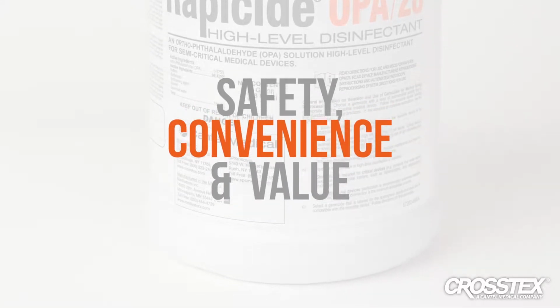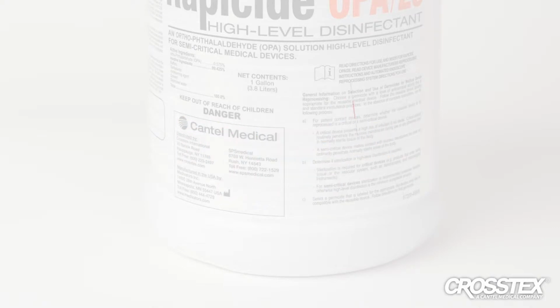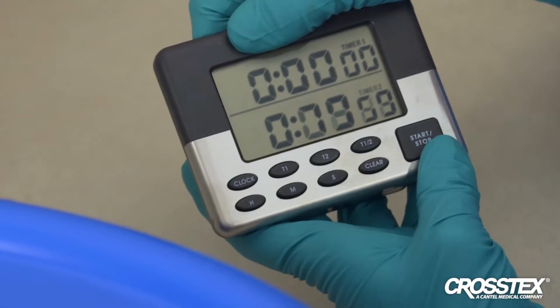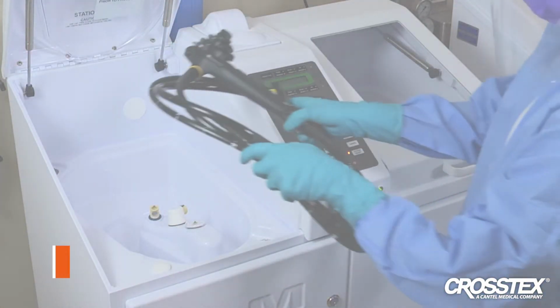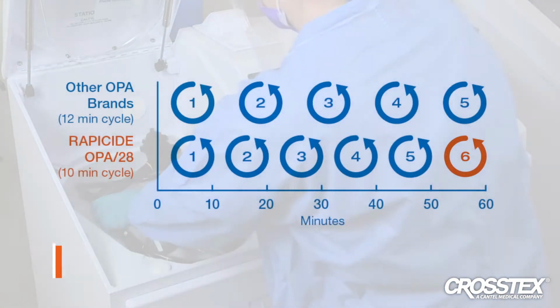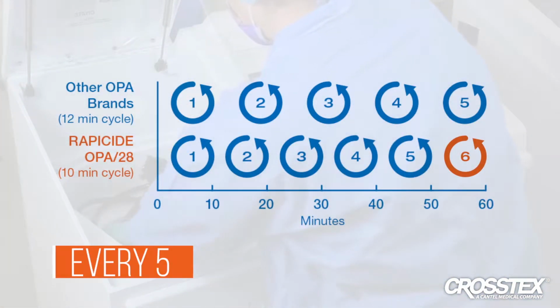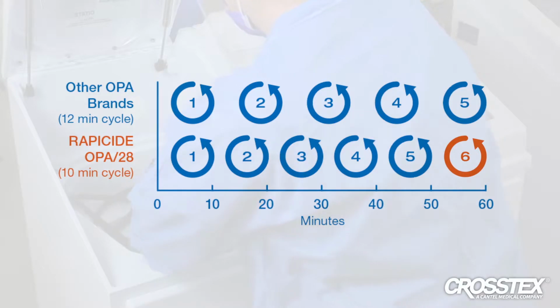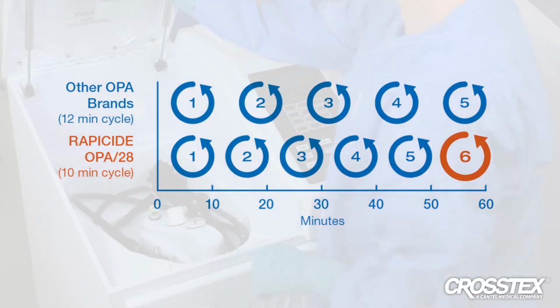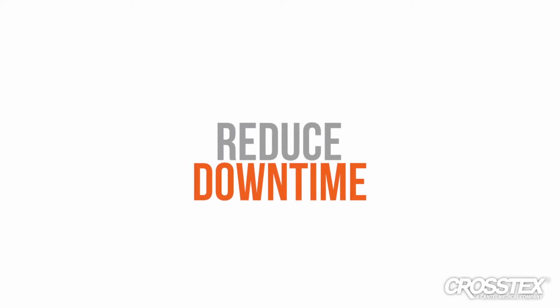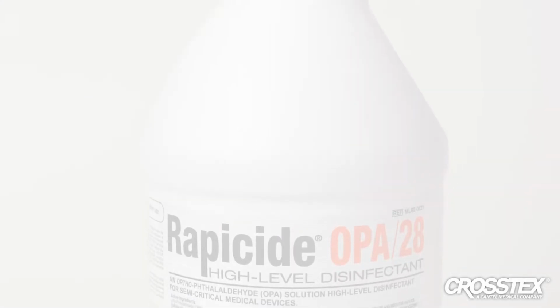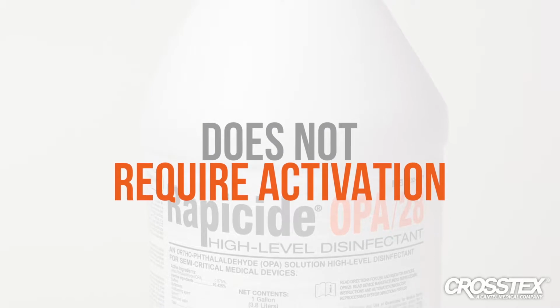and value. Rapicide OPA 28 10-minute manual disinfection contact time provides 1 extra disinfection cycle for every 5 instruments reprocessed, compared to 12-minute OPA, allowing you to reprocess 1 extra scope per hour and reduce downtime of medical devices. Rapicide OPA 28 is supplied ready to use and does not require activation.